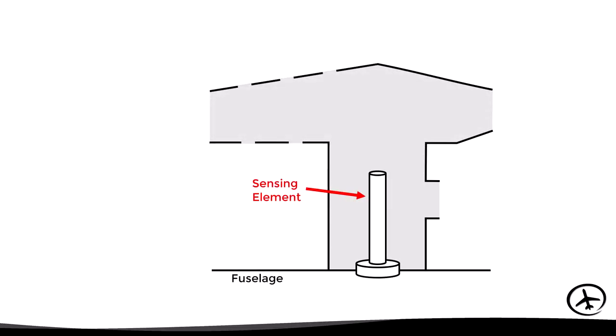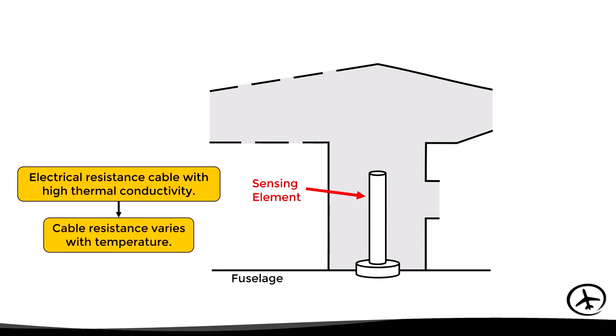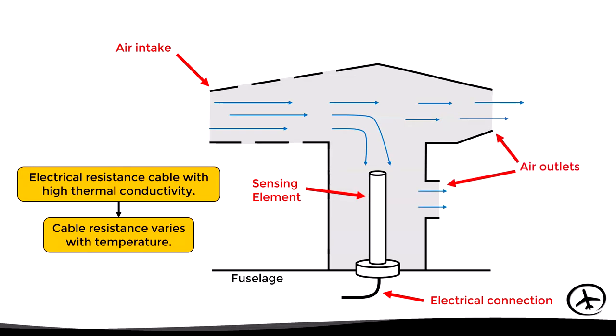Inside, we have the sensing element, which consists of an electrical resistance cable with high thermal conductivity. This means that the electrical resistance varies with temperature and can therefore be easily measured. The measured temperature is transmitted via an electrical connection to the instruments and other systems. Air enters through the intake, where part of it continues along and the rest passes around the sensing element before exiting through the air outlets. This design allows for a constant flow of air through the sensor and prevents water or dirt from accumulating inside the probe. The structure also has bleed holes which prevent excess pressure from building up inside.